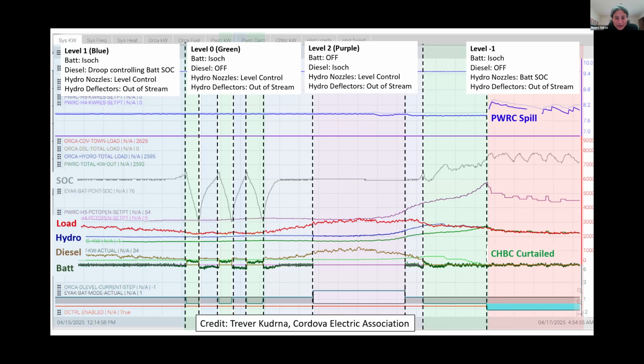As the hydro starts to pick up or the load starts to drop, they will put the battery in ISOC and run the diesel in Droop. The diesel is then being biased to control the battery state of charge. The hydro nozzles in all of these cases are just controlling the level of the water. If the hydro continues to go up or the load goes down, they go into level 0, which is the green, and they'll go into cycle charging mode.